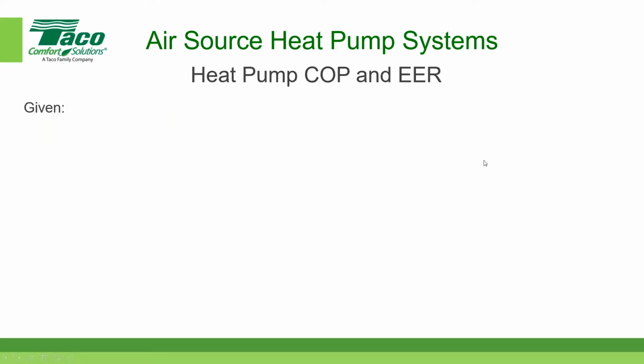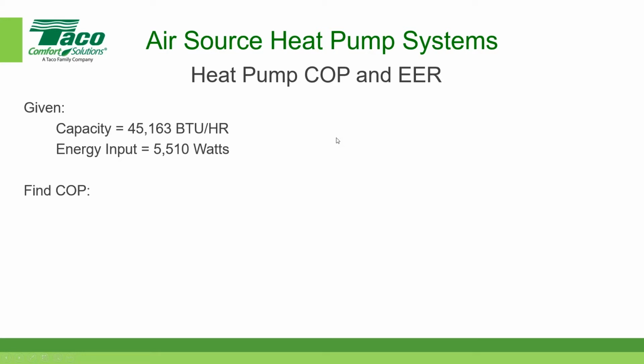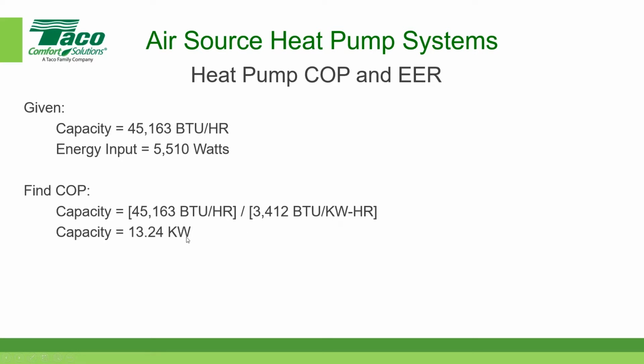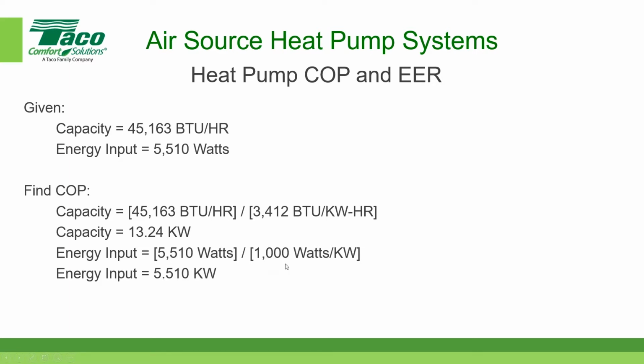So let's look at an example. If we were given a capacity of 45,163 BTUs per hour, and the energy input was 5,510 watts, because we want the capacity divided by the energy input, but they have to be in the same units, we have to convert a couple of these units. So let's find the coefficient of performance. We first take the 45,163 BTUs per hour and divide that by 3,412 BTUs per kilowatt hour, which in this case is 13.24 kW. Now we take the energy input, 5,510 watts, divided by 1,000 watts per kW, which is 5.510 kW. So that's the energy input.